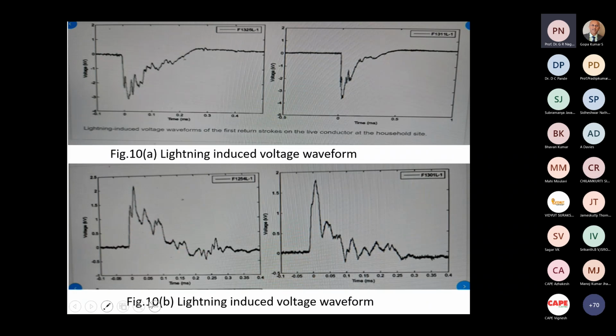And then you will see again the time scale is 0.05 milliseconds. That means this is about 50 microseconds. You see around 50 microseconds here, there is a huge oscillation. So what is it that you take here? Similarly here, what is it that you take? 50% is somewhere here. What is it that you take? The front is substantially good, beautifully I should say. 50% is here, but where's the tail time? So in reality, the time to front of a real life lightning wave is typically around 5 to 10, 15 microseconds. The time to tail, if you want to look at that, can vary from 15 to 20 to even hundreds of microseconds.